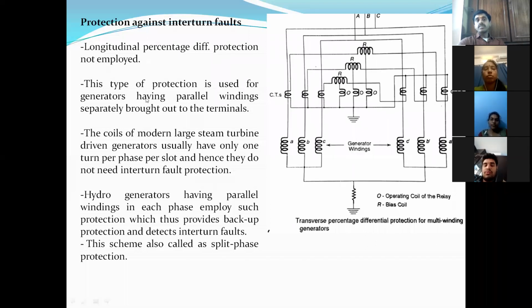This type of protection is used for generators having parallel windings with separately brought out terminals. The coils of modern large steam turbine driven generators usually have one turn per phase per slot, and that means turbo generators, steam turbines. Hence, they do not need interturn fault protection. But which type of generators need interturn fault protection? Hydro generators, having parallel windings in each phase. Every phase will have parallel windings. Why do we need parallel windings? To have more current. So protection is required which provides backup protection and detects interturn faults.